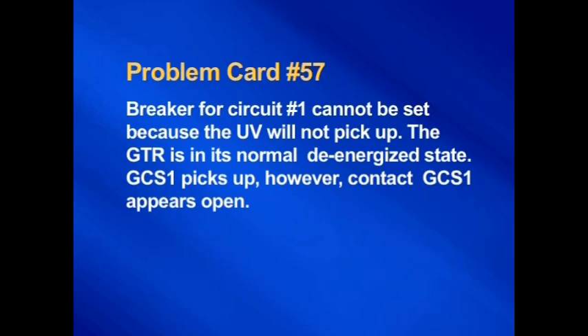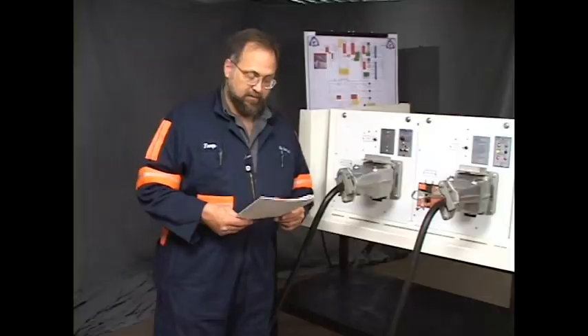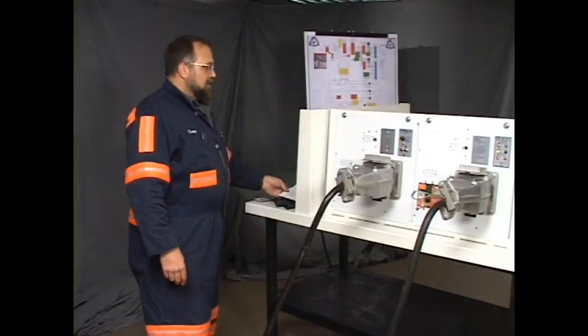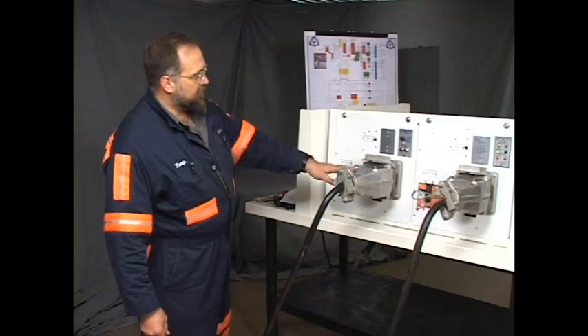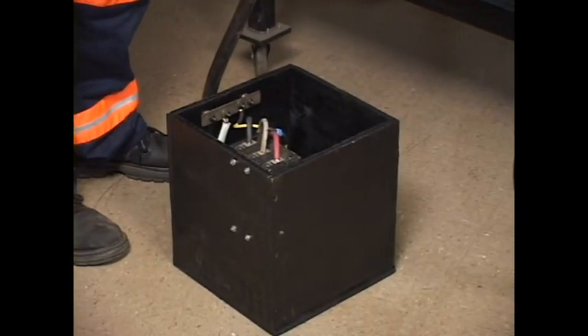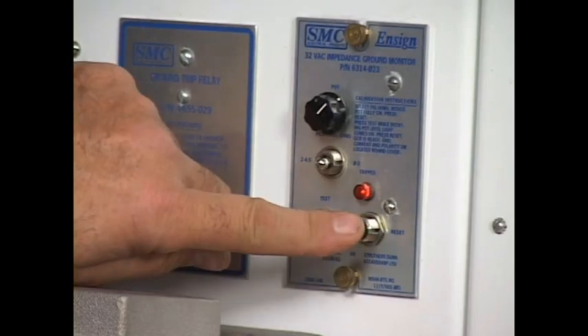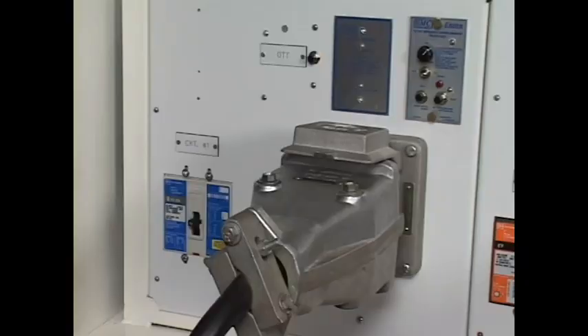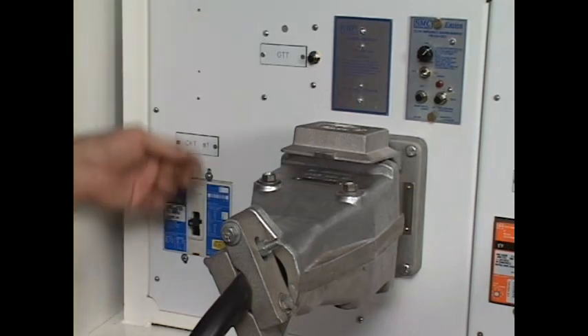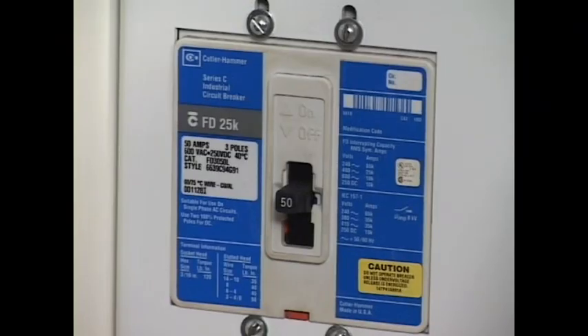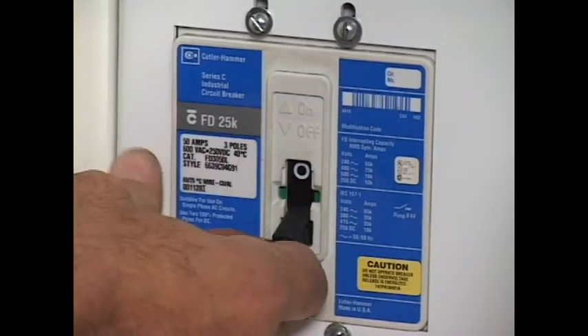Problem card number 57. The breaker for circuit number 1 cannot be set because the UV will not pick up. The GTR is in its normal de-energized state. GCS1 picks up, however the contact GCS1 appears open. On this problem, we have circuit number 1, the machine's plugged into it. We reset our monitor. It resets. We attempt to energize circuit number 1 by closing circuit number 1 breaker. It won't go in. It stays in a tripped position.